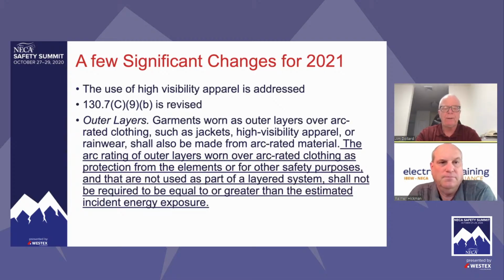Yeah, thank you, Palmer. And one of the things that we saw was people using flammable high vis apparel. That's a really big problem. We need to keep in mind that we strive for perfection when it comes to the arc flash hazard. We're never going to get it perfect. The key is to get people out of flammable clothing. People aren't getting killed and seriously injured because they weren't wearing the right level of arc rated clothing. They're getting killed and injured because they're not wearing arc rated clothing. They're wearing flammable clothing. We get clothing ignition and it's game over.